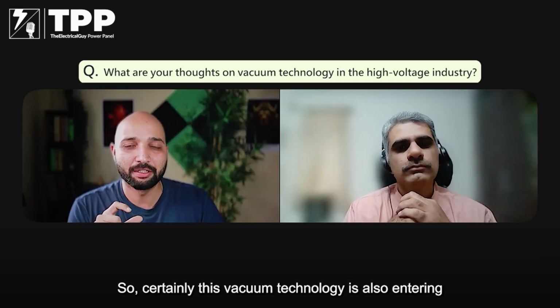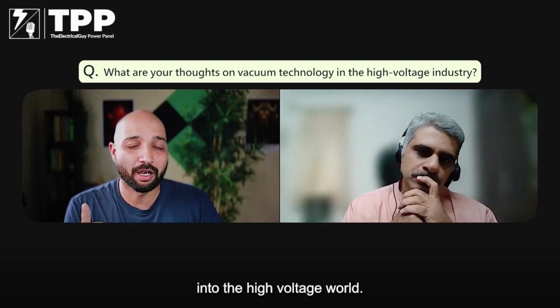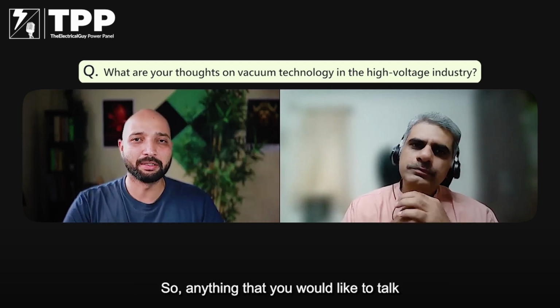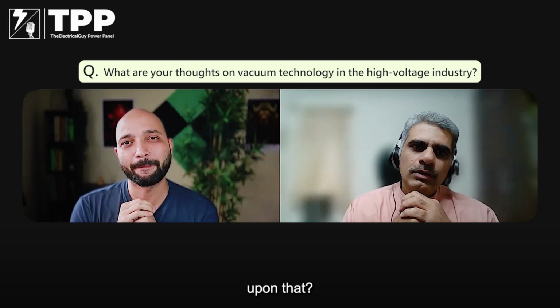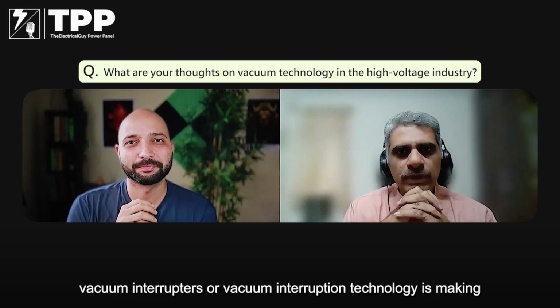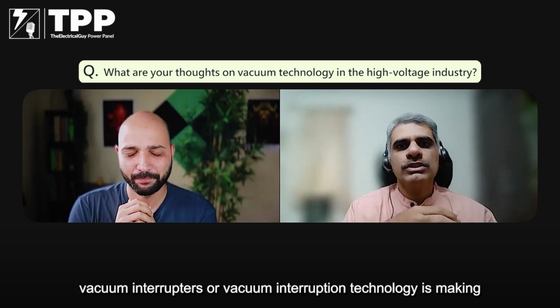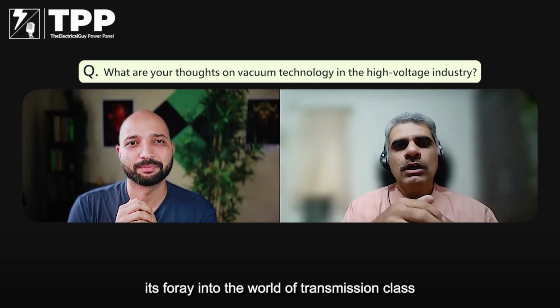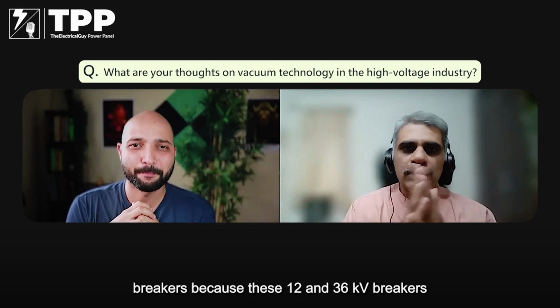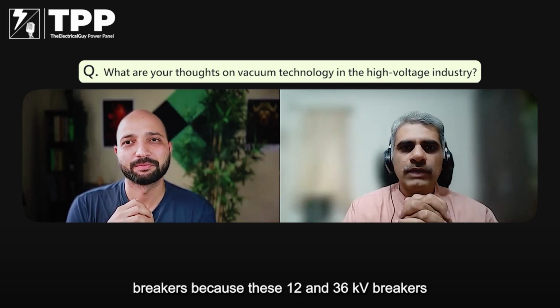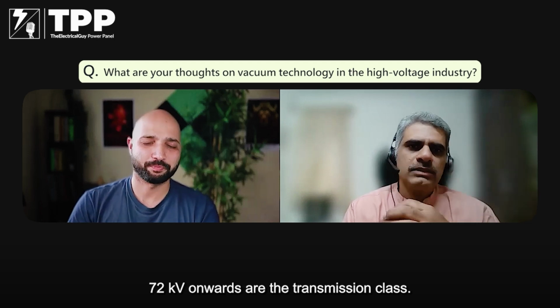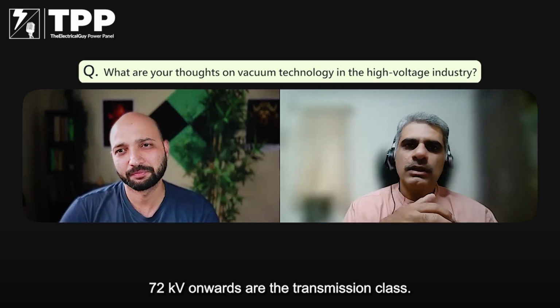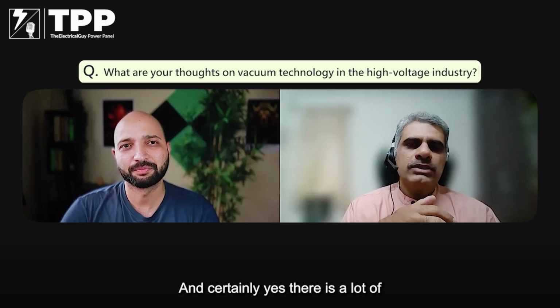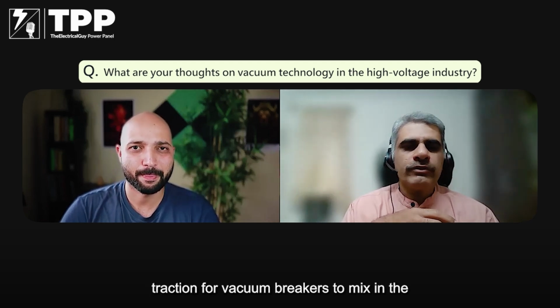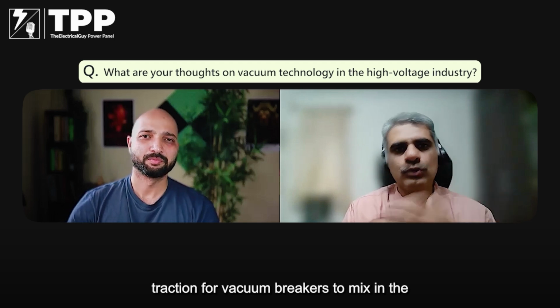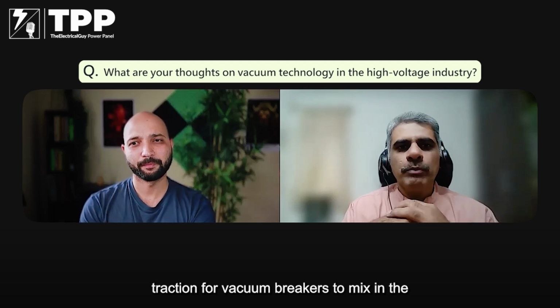So certainly this vacuum technology is also entering into the high voltage world. Anything that you would like to talk upon that? Yeah, certainly. As you rightly said, vacuum interruption technology is making its foray into the world of transmission class breakers, because these 12 and 36 kV breakers we call distribution class. 72 kV onwards are the transmission class.